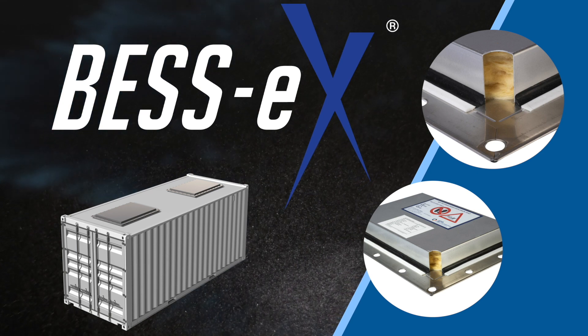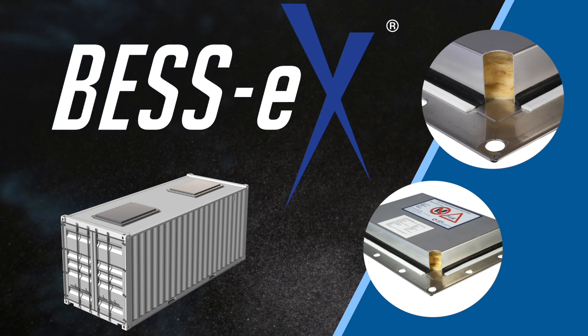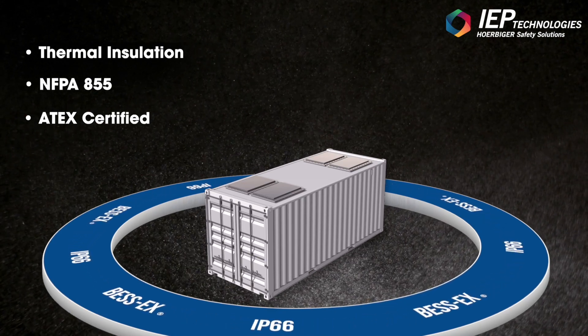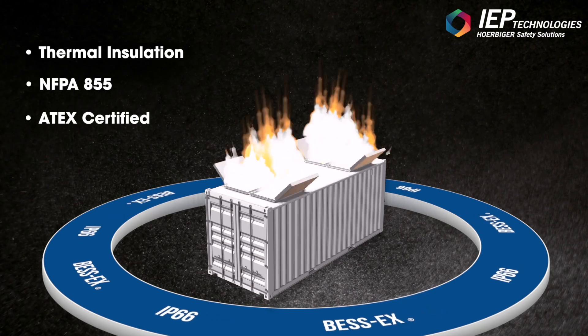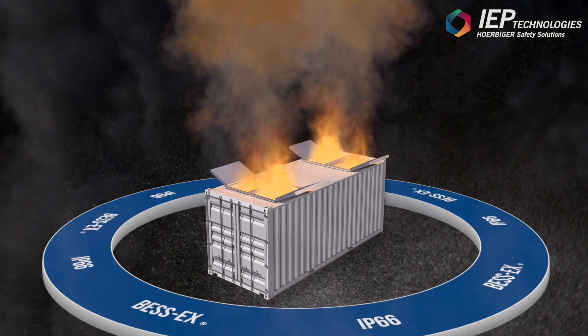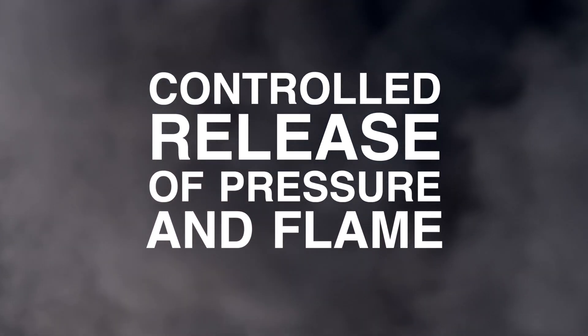IEP BESS-eX vents are ATEX certified and comply with NFPA 855 requirements. Specifically designed to meet the challenging environmental requirements of a battery energy storage system, the BESS-eX vent is rated to IP66 and is thermally insulated. Pressure and flame are relieved during an explosion event, and the BESS-eX vent also protects the battery energy storage unit from weather ingress during normal operations.